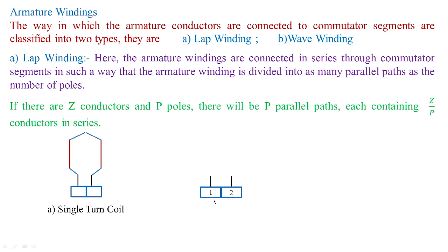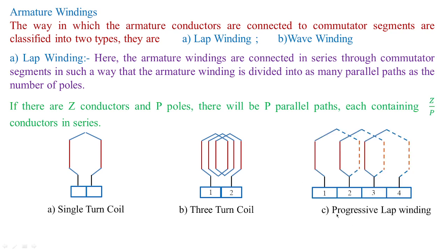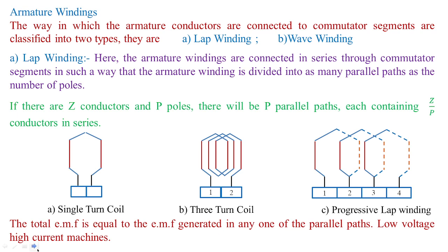For example, you can have two commutator segments connected to the armature such that on the left side you have three conductors and on the right side three conductors — one representing north and one south. This type of connection is regarded as a three-turn coil. Likewise, you can have n-turn coils for different types of connections. Generally we employ progressive lap winding. The total EMF equals the EMF generated in any one of the parallel paths. This type of connection is generally employed for low voltage and high current machines.